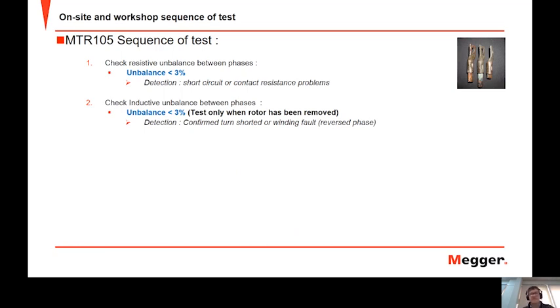We should then check the inductive balance between phases. Again, we're looking for about 3%. However, we have to consider that when the motor is assembled, the rotor can affect the inductance of the phase or phases. So this depends on the design of the rotor and also the air gap. Some rotors have very little influence on the stator inductance. Others have quite a big influence. So if you know there's no influence, then you can use inductance testing with the rotor present. If it causes a big unbalance, then you can only really use the inductance when the rotor has been removed. And again, we're looking for shorted turns or that winding fault, reverse connection, reverse phase.